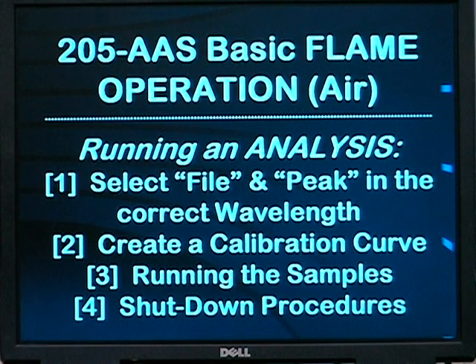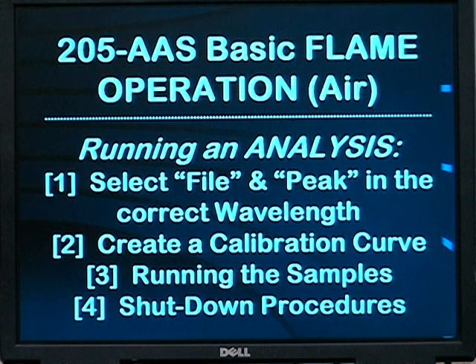For basic operation of the 205 AA with an air acetylene flame system, you need to turn the instrument on and select the proper element file from the library included on the system. After that file is selected, you will then peak in the wavelength for the hollow cathode lamp that is inserted in the turret. Then you need to create a calibration curve suitable for that element. Once a satisfactory calibration curve has been created, you can run your samples, and then there are some basic guidelines for shutting down to ensure the stability and long life of your instrument.